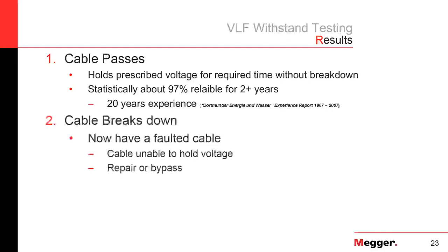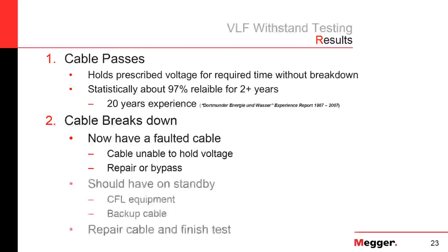If the cable doesn't pass, then the cable breaks down, and we now have a faulty cable. We need to repair or bypass that cable. That means that when we do this type of testing, we should have fault location equipment on standby, backup cables on standby, splice kits on standby, things like that.